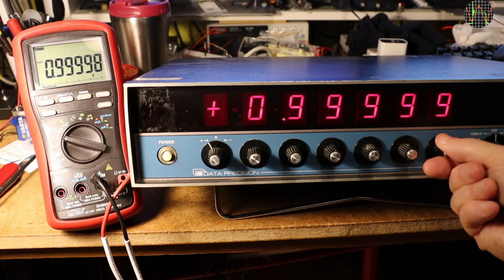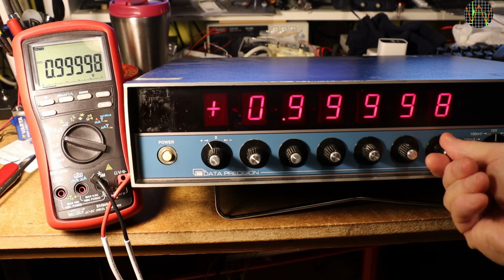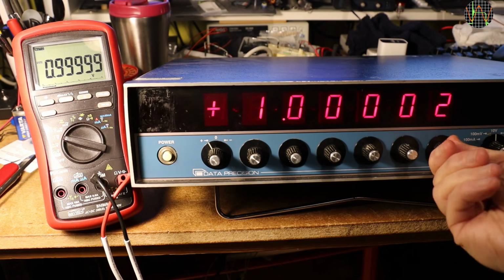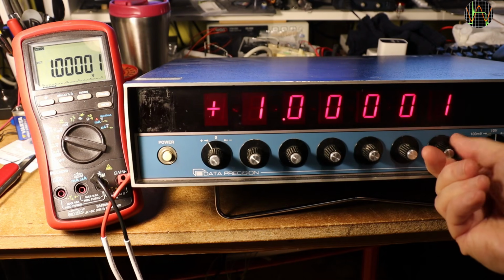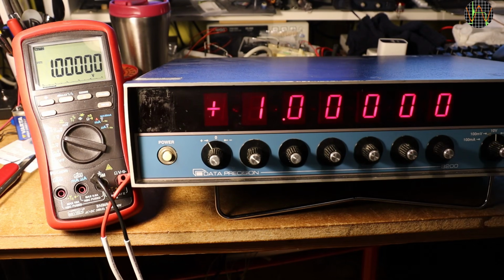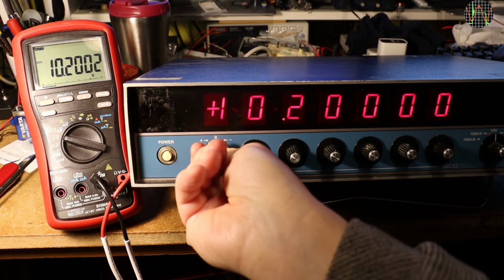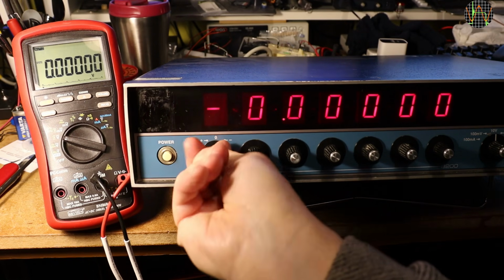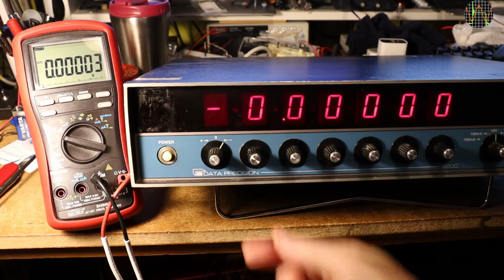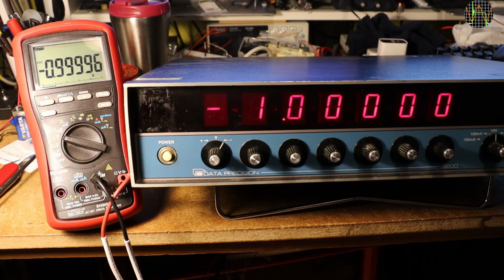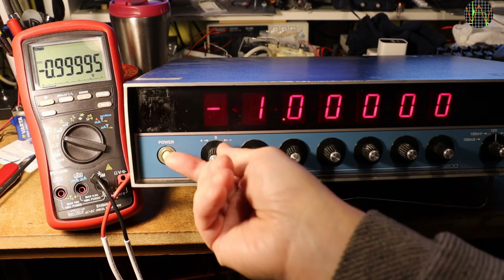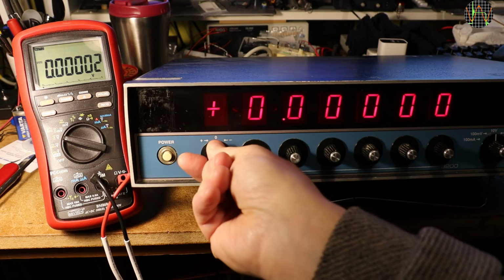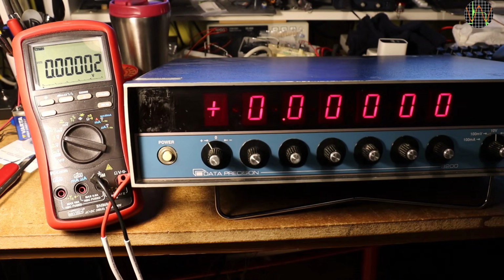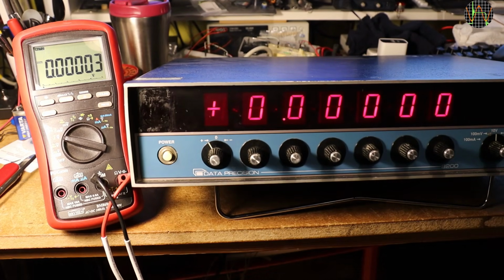While the 8200 has a knob for every digit like other calibrators, the microprocessor implements a smart and convenient rollover that many other calibrators do not have. On the flip side, other calibrators may not reset the dialed-in number when switching polarity like the 8200 does. In fact, I often simply reverse the banana plugs, which is faster than re-entering the desired number, especially if you have to do the polarity switching a number of times.